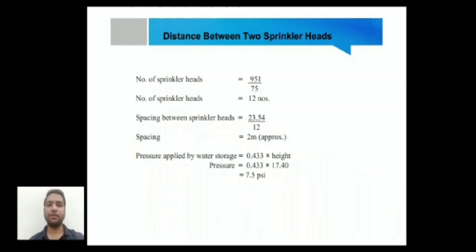Now the pressure applied by the water storage is gravity-applied pressure. So we have tried to pressurize the water by gravity. So we have calculated the water storage pressure. There is a standard formula for calculating water storage pressure according to gravity, which is 0.433 into height in feet. So 0.433 into 17.40, and this height is from the ground level, because gravity is calculated from the ground level. Now it has come to 7.5.